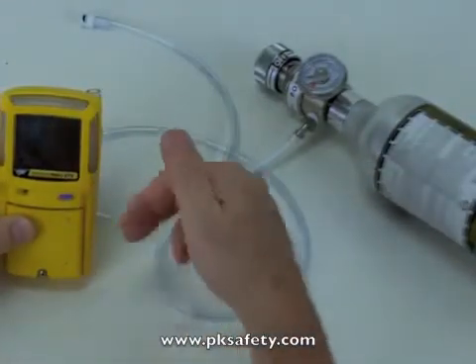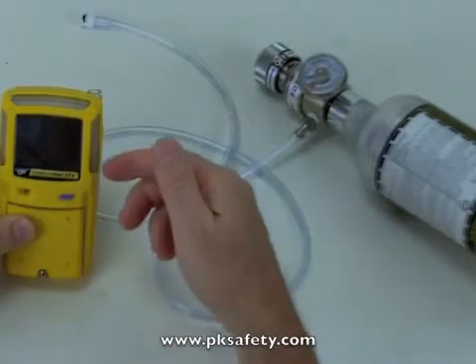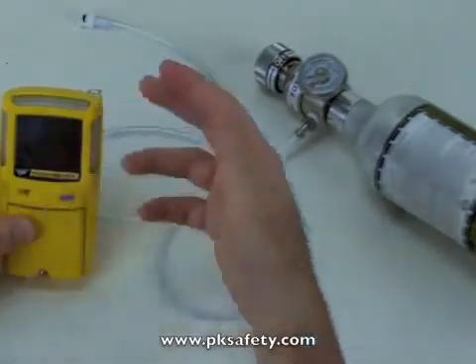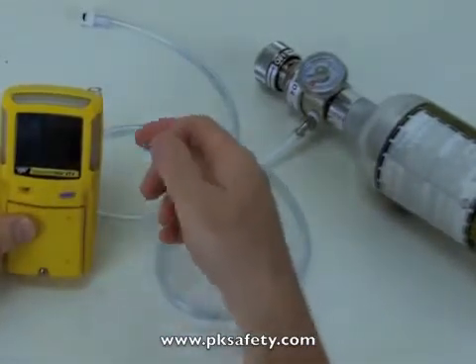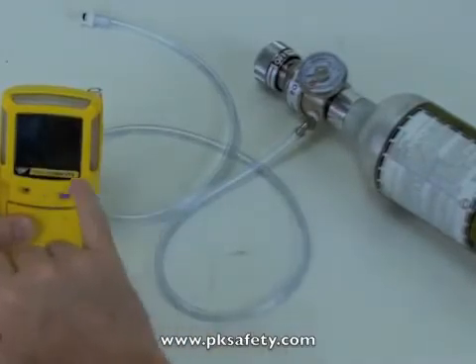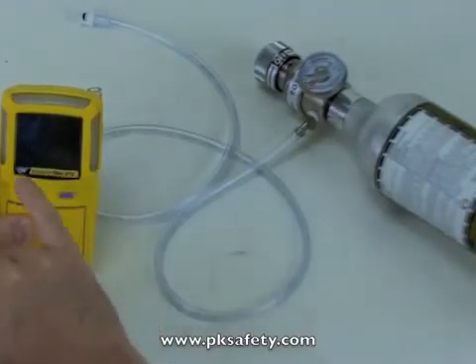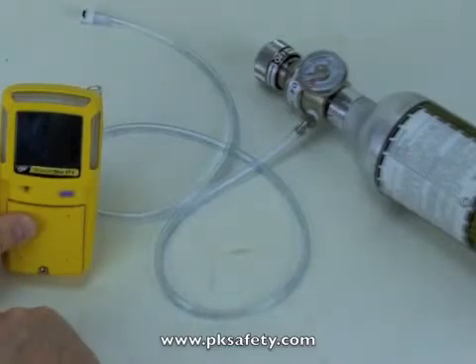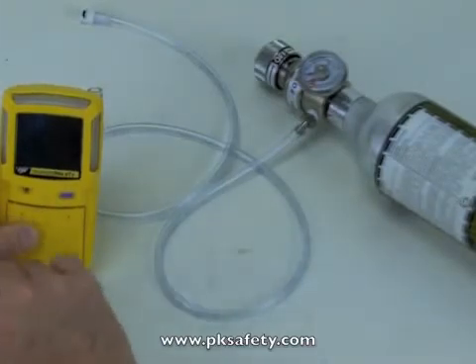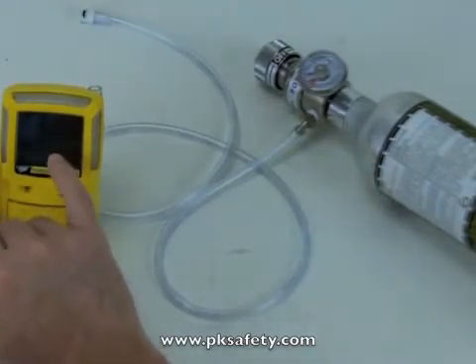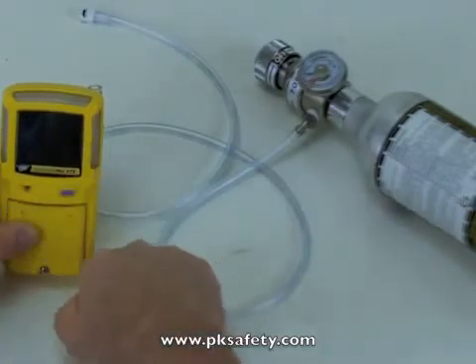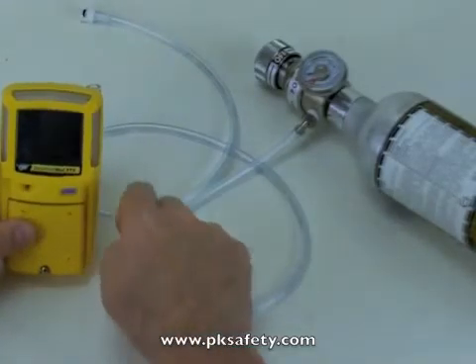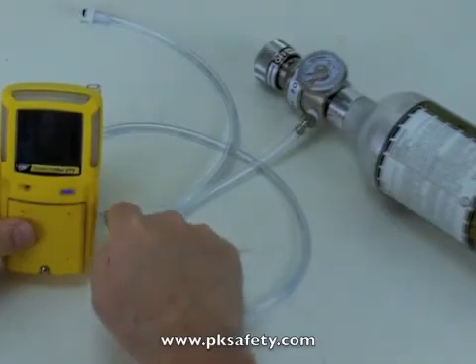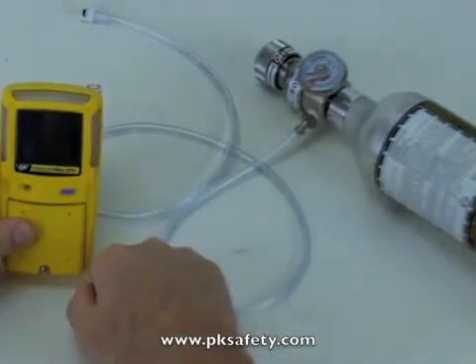So now the readings are going back to 0 as the sensors have been flushed with fresh air. So we're reading 0 across the 2 toxics and the LEL and 20.9 in the O2. The instrument is now calibrated and ready to go. The cal has now been reset as a countdown from 180 days. I don't recommend that you wait 180 days to calibrate this instrument, but that's the way the factory sends it.